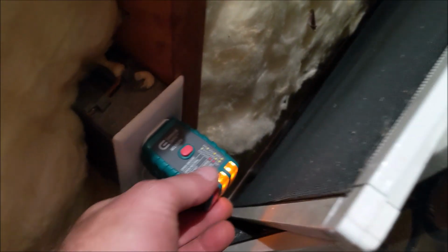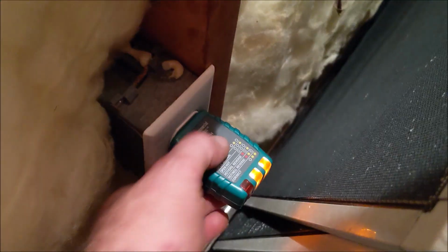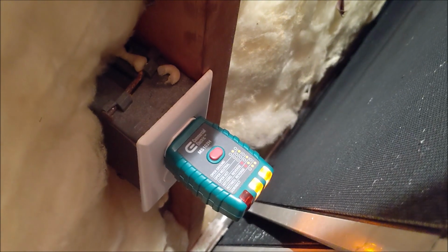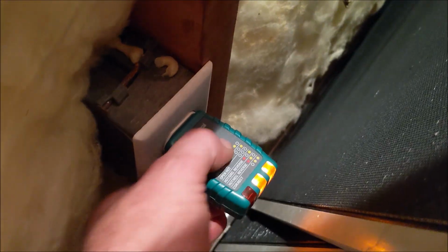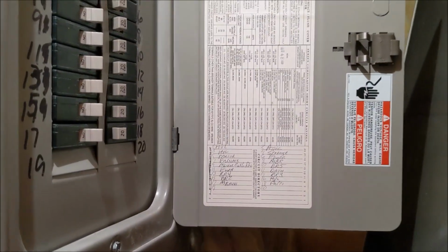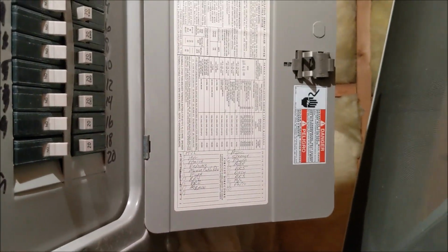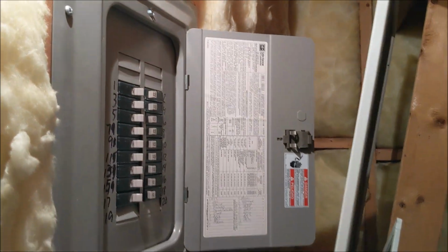Here we have an outlet in the attic, and it's good polarity, two oranges, that's good. And I'm going to go ahead and simulate a ground fault circuit like someone's getting shocked, and it doesn't trip. So we do recommend GFCIs, especially around service equipment. And here we have a Cutler Hammer sub electrical panel, and it looks like everything's labeled pretty well. We're getting ready to open it up and take a look.